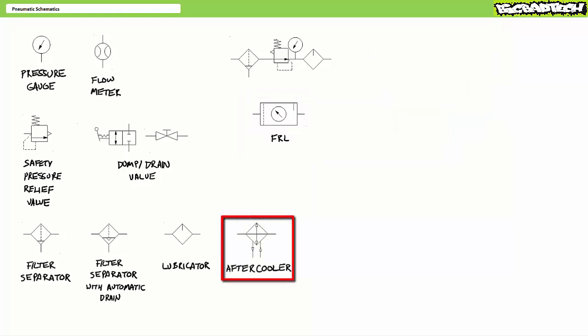After coolers are heat exchangers schematically represented as diamonds with arrows pointing away from the air to be cooled passing through the center. If an after cooler makes use of a liquid or an air heat transfer fluid or HTF, the HTF is routed counter to air flow. This counter flow arrangement ensures that continual temperature gradient occurs the length of the after cooler tube and shell heat exchanger.